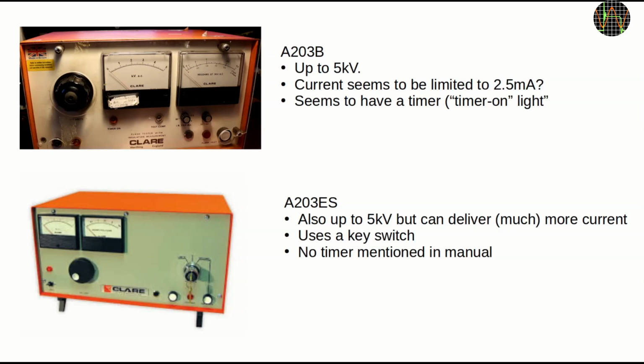The only user manual I found was for the more modern but also obsolete A203ES. I did not find any service manuals or schematics of any of these units. Just from a quick glance, the A203ES user manual seems to be of limited value for my unit. The two look and seem to be quite different. The A203ES has various current delivery settings controlled by a key switch, and there is no mentioning of a timer in the manual. The controls in my unit seem to be for the meter, not the actual current delivery, but judging from the timer on light, there appears to be a timer.